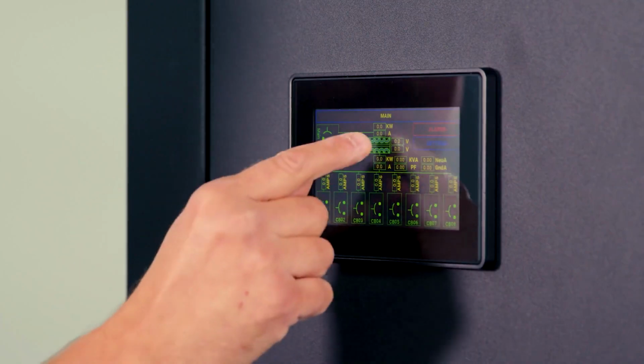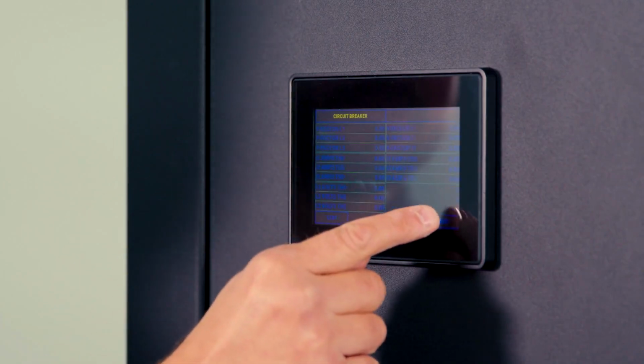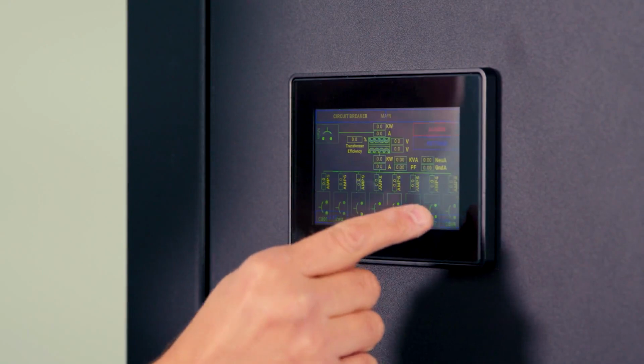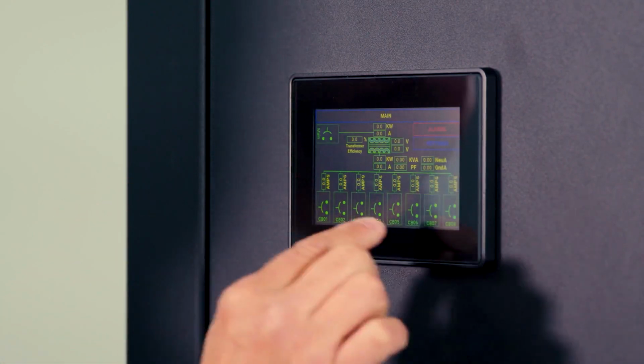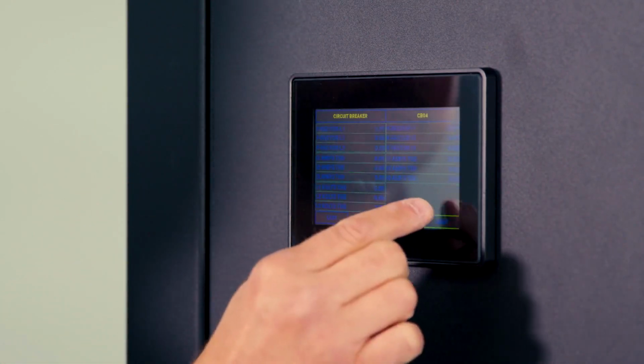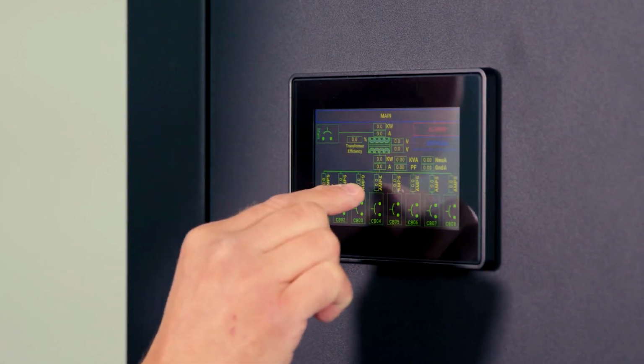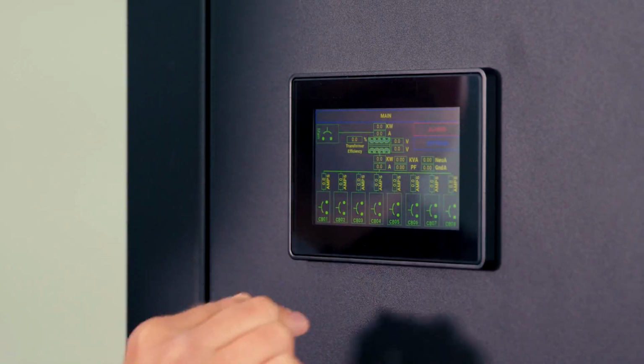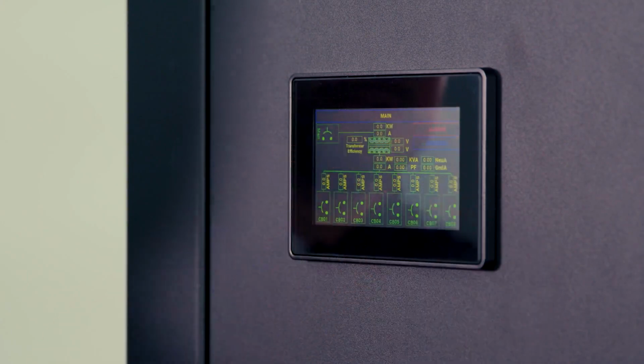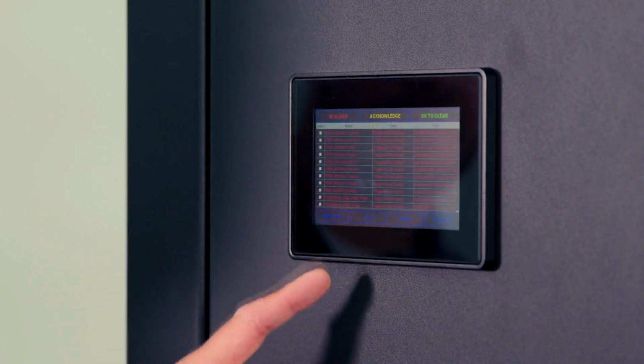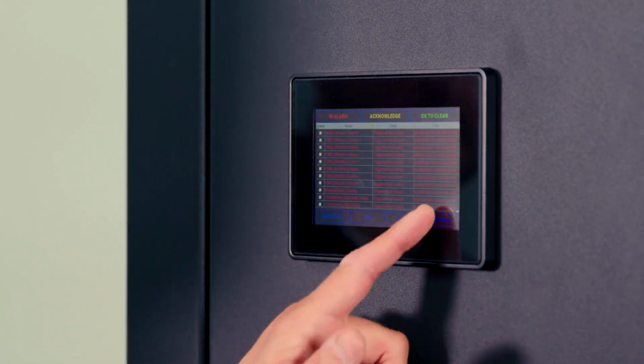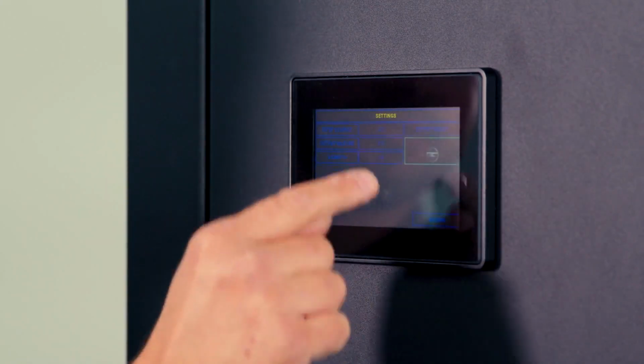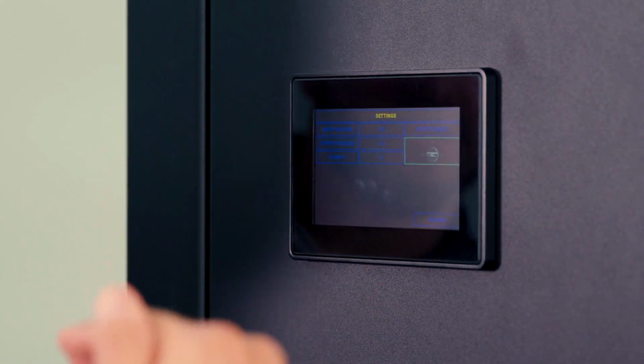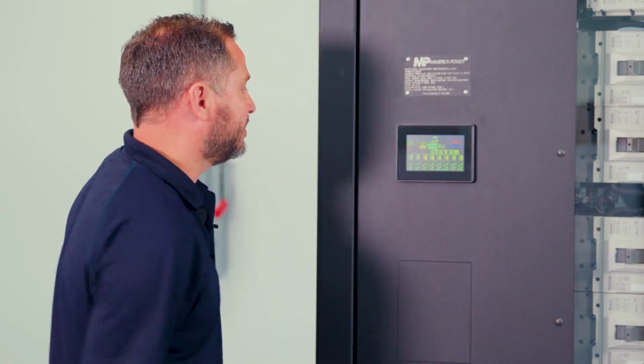The same thing we can see on our secondary side as well, same information. And as well as all of our feeder breakers. You can go through each one and check that as well. You can see all of our information for our kW, our amperages, our neutral amperages, all the information is there. We can actually go to see our alarms as well, which can be recorded and all time stamped. We can go to our settings. Right now we have all this enabled. We can change our voltage settings to 415, 400, or 208. And that is basically the gist of our HMI.